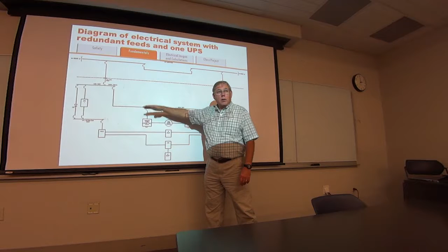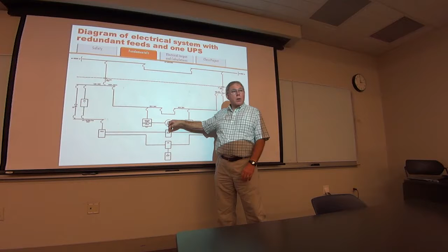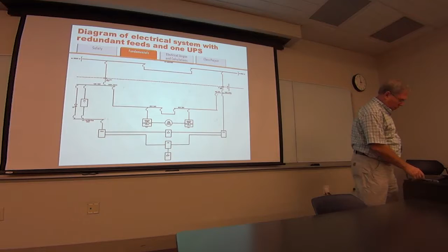Thing kept running. So with this UPS, I had to put a cold water storage because if I get a big power quality event, these chillers will drop offline. And when they drop offline, they got to restart. It takes them 10, 15 minutes to restart sometimes, maybe 10. In the meantime, you pump water out of your cold water storage tank while you're waiting on that, right? All right, it's really getting expensive here.